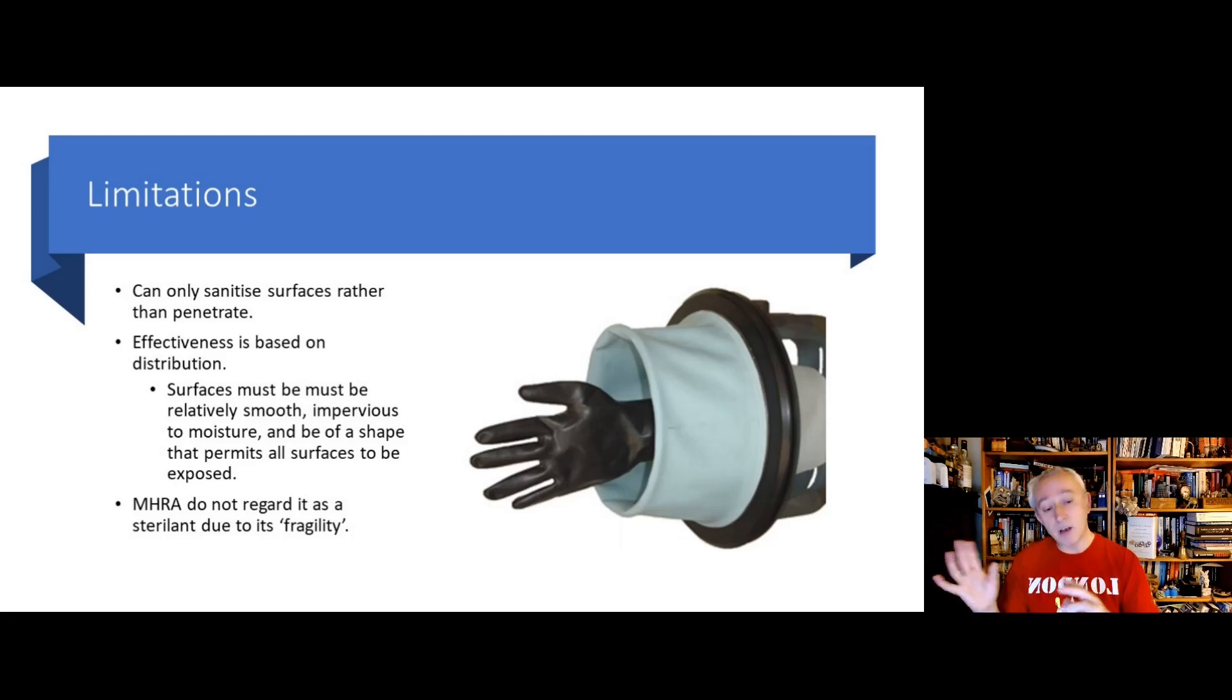It's also, by bodies like MHRA, seen as a little bit fragile in that you can get variations that affect the distribution if you get slight tweaks of temperature and humidity. It's not quite as robust as other decontamination sterilization methods. And that distribution also comes down to the quality of the surface. It's only really going to work effectively with smooth, impervious surfaces.